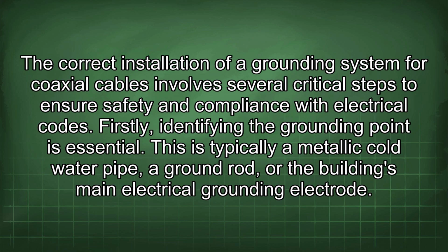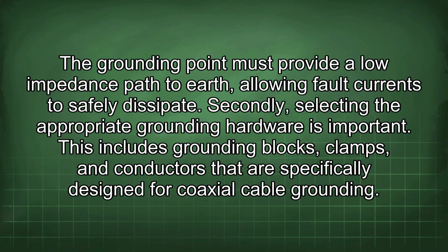The correct installation of a grounding system for coaxial cables involves several critical steps to ensure safety and compliance with electrical codes. Firstly, identifying the grounding point is essential. This is typically a metallic cold water pipe, a ground rod, or the building's main electrical grounding electrode. The grounding point must provide a low impedance path to earth, allowing fault currents to safely dissipate.